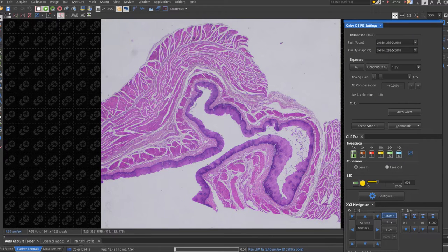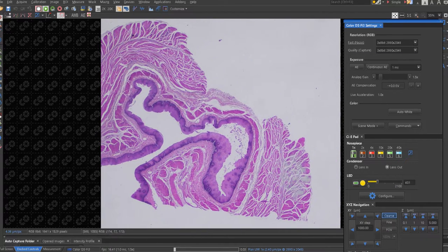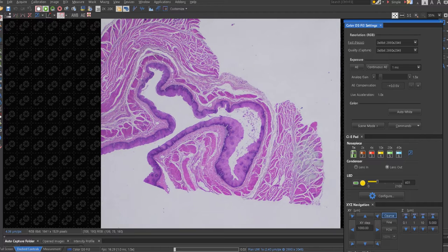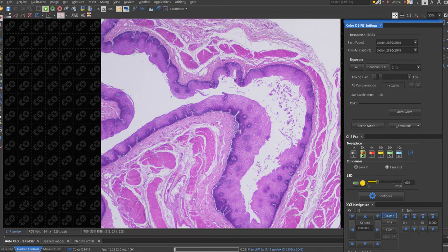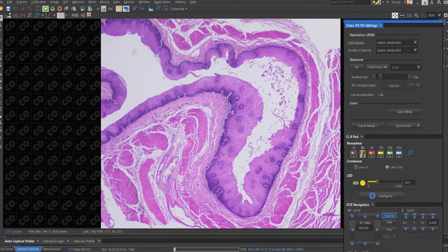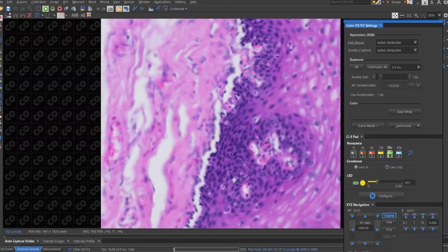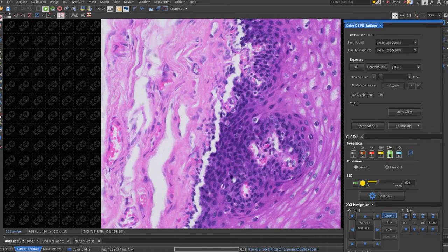Let's have a look. Let's say a pathologist wishes to view a slide prepared in the frozen section lab. He or she can have the slide sent to them, or the sample can be mounted on the microscope in the frozen section lab and be looked at in real time in the pathologist's office. The pathologist is not at the mercy of the person at the other end. Indeed, no one need be there once the stage is loaded. The pathologist can then scan the slide, change magnification, and capture images from their desk. Remote access and control also opens the possibility of long-distance consultation.